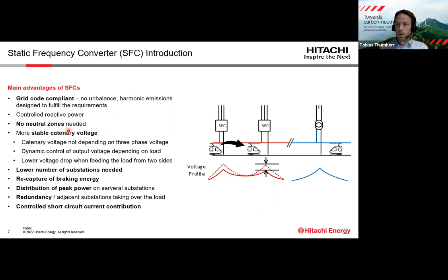As said, we don't need neutral zones, and this has the advantage that there is a saving because of that. It also has other advantages connected to that. We have a more stable catenary voltage, so the catenary voltage does not depend on the three-phase voltage. It's independent. It's basically given by the SFC control. And then we can have dynamic control of the output voltage depending on the load.